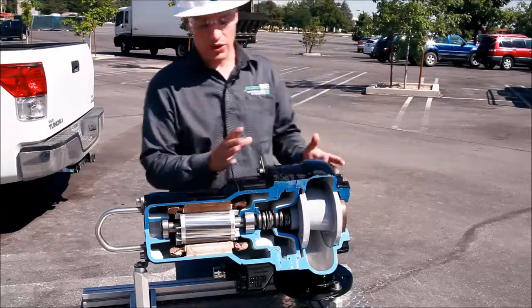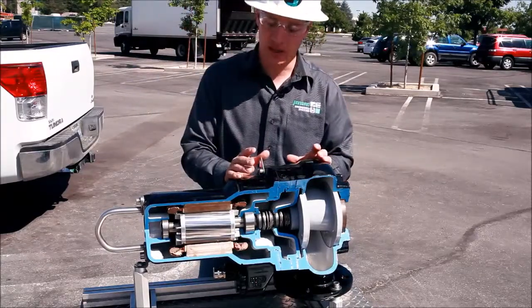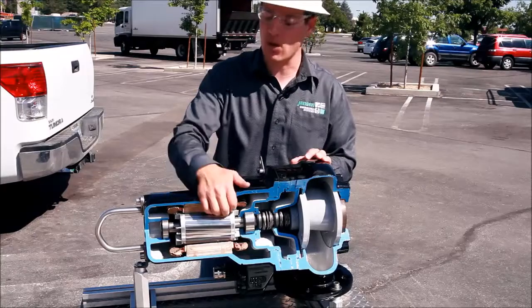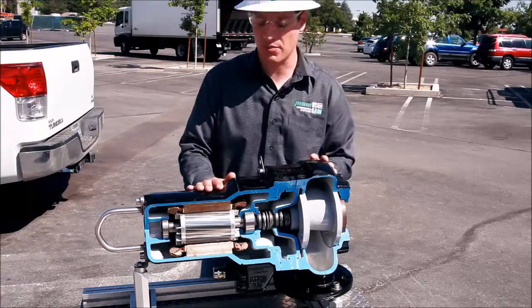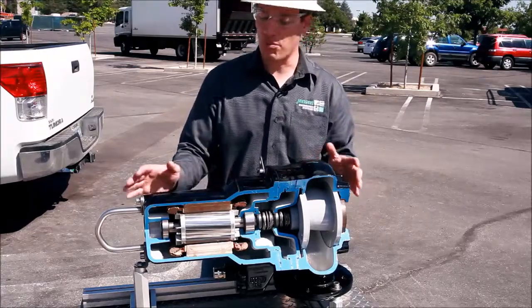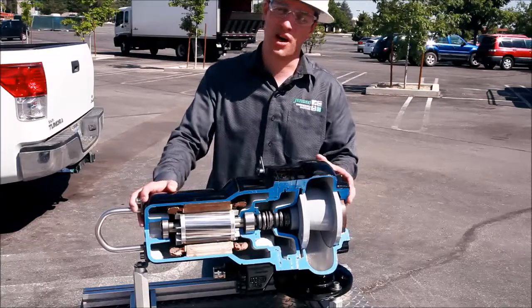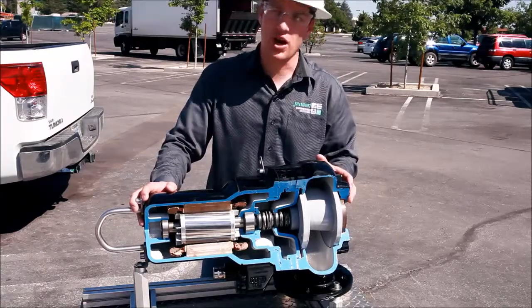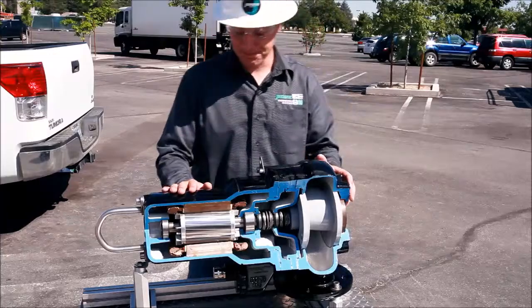Now, if water gets in the oil chamber, that does not create a situation where we immediately have to stop using our pump, because water has not entered the motor assembly yet, so the pump's still operational. It does mean, however, that we want to pull the pump as soon as possible, get it to an authorized HOMA motor service shop, and get those seals replaced.